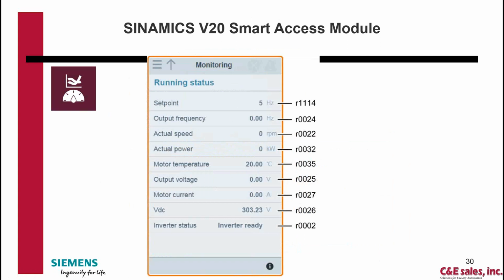Monitoring page is going to show you these parameters, basically similar to what we saw on the jog screen, but this is going to be, when it's normally running, what the set point is, what the output frequency is, actual speed and RPM, actual power in kilowatts, motor temp, output voltage, motor current, and volts DC would be your DC bus voltage, and inverter status.